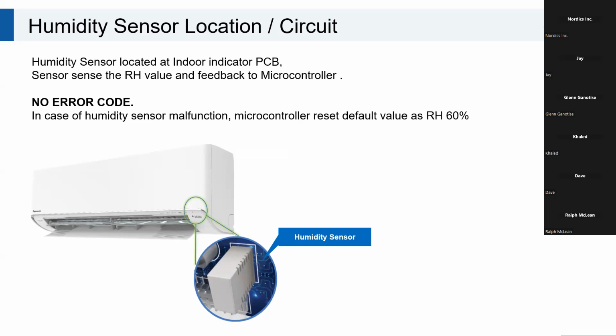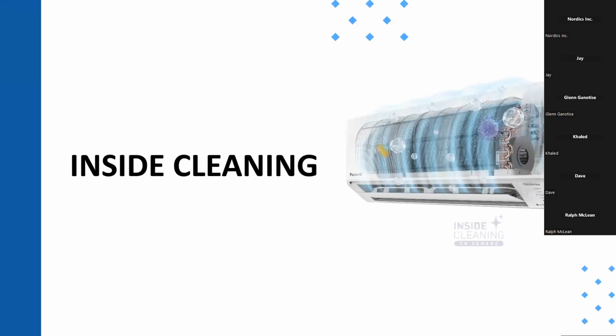The users who use this mode, the dry plus humidity sensor, will perceive that humidity has increased. Then if it goes beyond 60%, by default, whenever it is faulty, the PCB controller will bring the dry mode back to 60% relative humidity. So you may have a complaint from users that the humidity level is still high and it doesn't work. Then you will come to know that maybe the sensor is faulty, because there is no error code generated for this. So that is how we can know that the humidity sensor is not working.